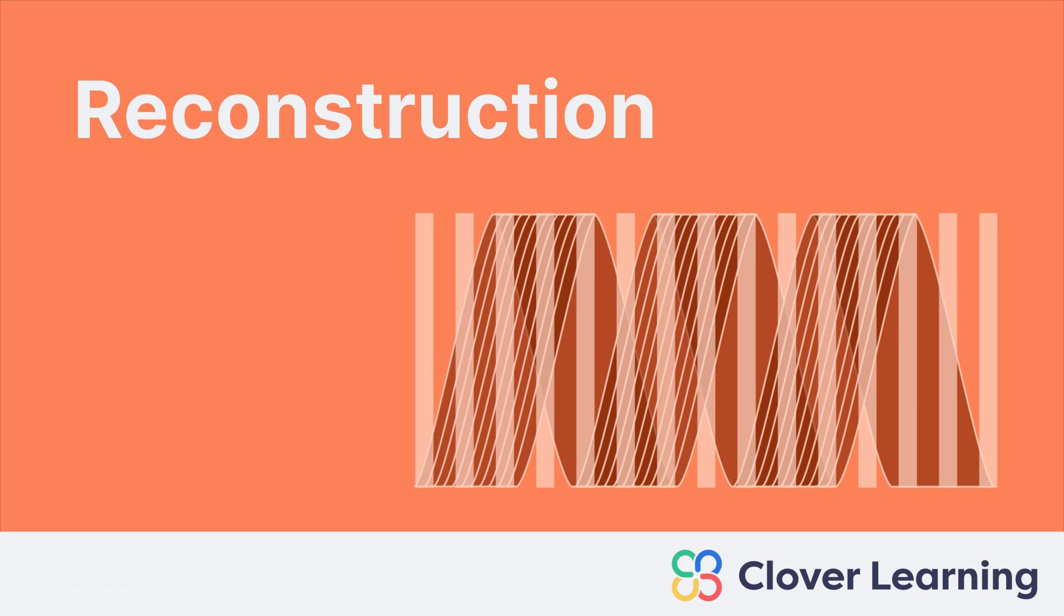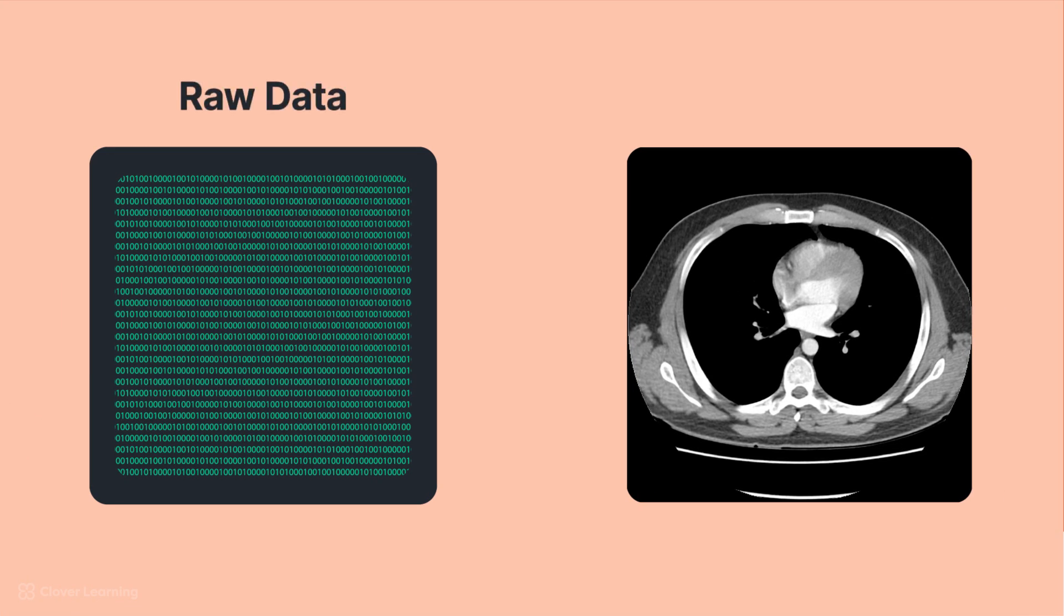This lesson is about an important part of CT image processing called reconstruction. The digital signal leaving the data acquisition system is considered raw data. It cannot be viewed by technologists because this information is unprocessed data, sometimes called scan data. Reconstruction is the process through which this raw data becomes image data or processed data. Raw data is stored only in the CT control console, but the image data is what's sent to PACS for the radiologist's interpretation.